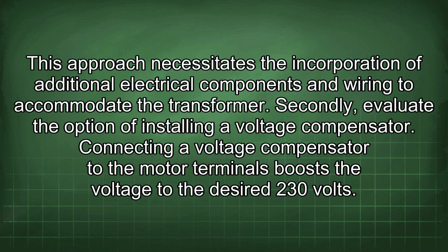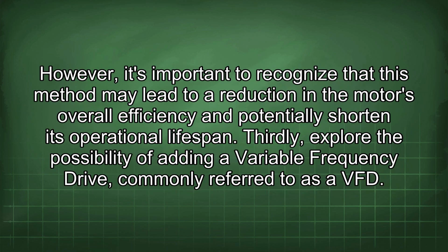Secondly, evaluate the option of installing a voltage compensator. Connecting a voltage compensator to the motor terminals boosts the voltage to the desired 230 volts. However, it's important to recognize that this method may lead to a reduction in the motor's overall efficiency and potentially shorten its operational lifespan. Thirdly, explore the possibility of adding a variable frequency drive, commonly referred to as a VFD.